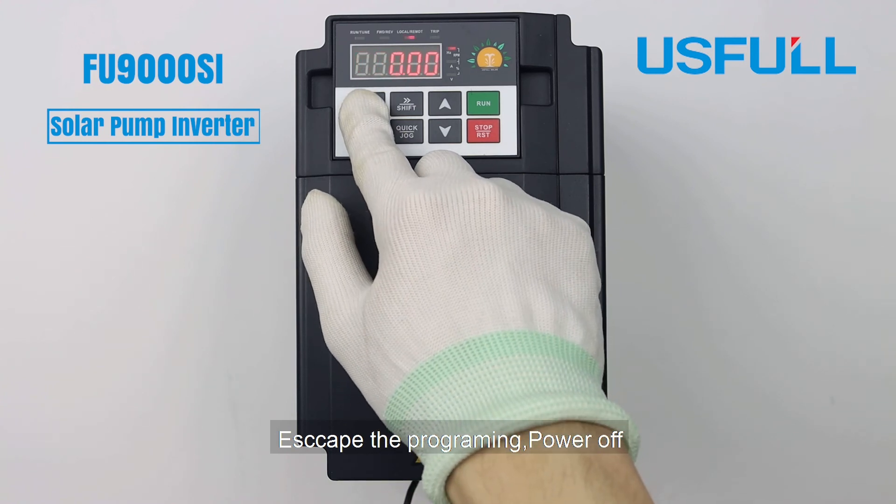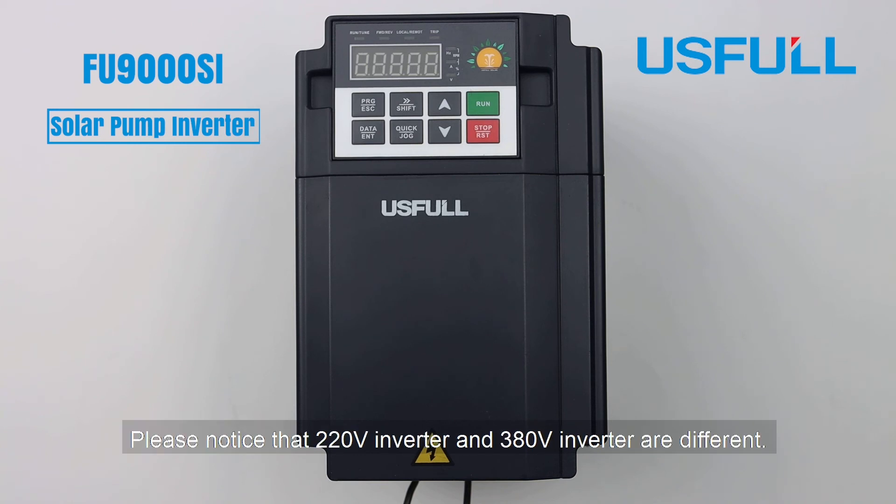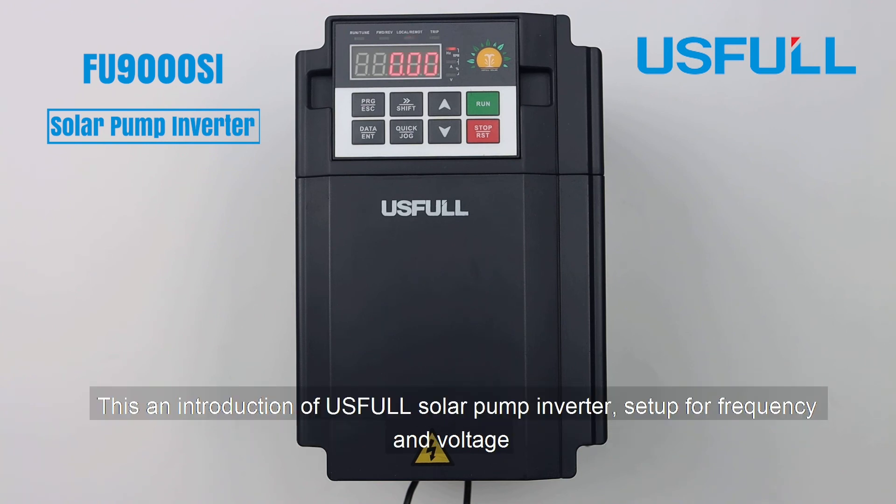Escape the programming mode and power off. Power on again and the setup is finished. Please notice that 220 volt inverters and 380 volt inverters are different — do not use a 220 volt inverter for a 380 volt system. This completes the introduction to setting frequency and voltage on the USFULL solar pump inverter.